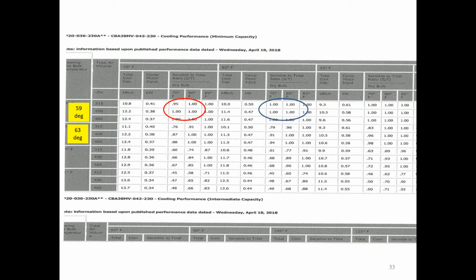So again, proper load calculations, which I know is very important to HC Blake, and I know that you guys do a great job of that. If you're on the bubble, call me if you want to discuss it. I'm happy to do so. If you're on the bubble, I would make every arrangement to either seal the ductwork up and make it tighter, or add attic insulation or whatever to try to keep that unit. You don't want to go from a 3-ton because we're right on the bubble and go to a 4-ton. It won't function or operate correctly.